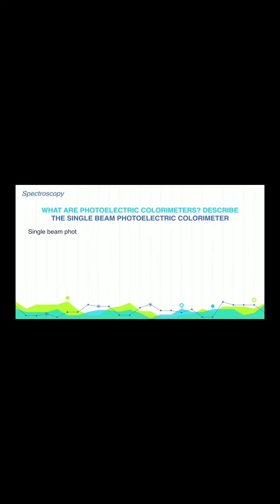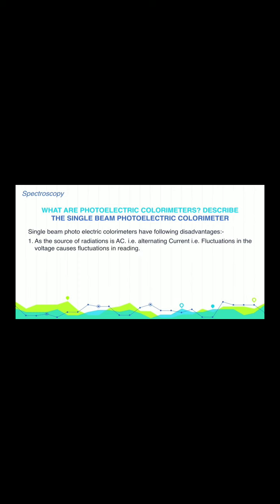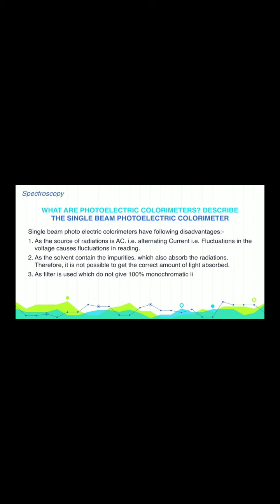But single beam photoelectric colorimeter has a lot of disadvantages. So what are these disadvantages? First, as the source of radiation is AC, that is alternating current, the fluctuation in the voltage causes fluctuation in readings. Second, as the solvent contains impurities, which also absorb the radiation, it is not possible to get the correct amount of light absorbed. Third, as filters are used which do not give 100% monochromatic light, the analysis is not accurate and has some errors.